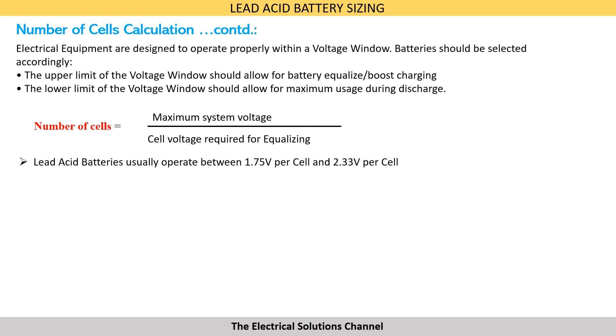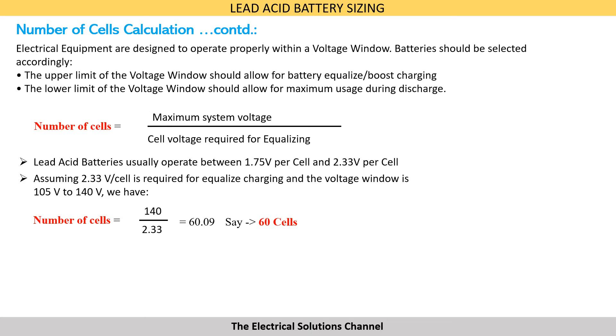Lead acid batteries usually operate between 1.75 volts per cell and 2.33 volts per cell. Assuming 2.33 volts per cell is required for equalizing, and the voltage window is 105 volts to 140 volts for a 125-volt battery, we have number of cells equal to 140 divided by 2.33, which equals 60.09. So let's say we select 60 cells.